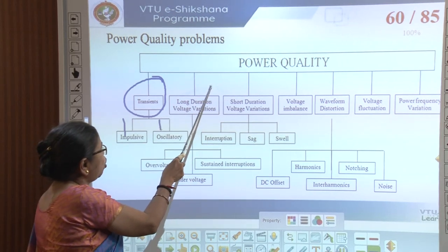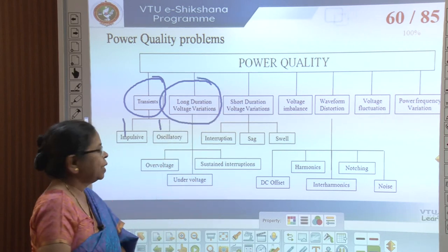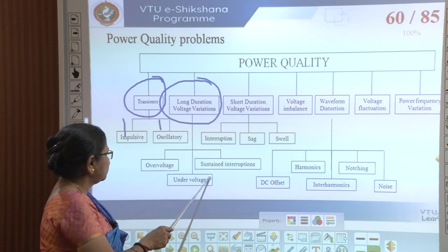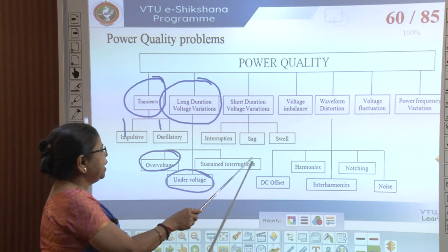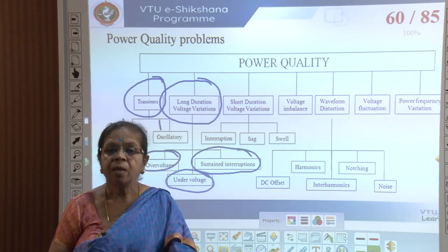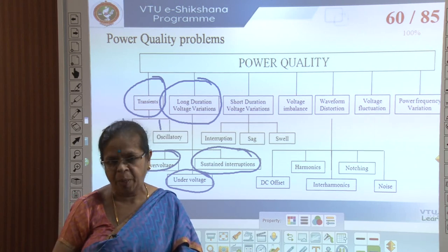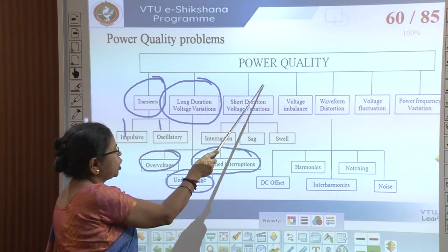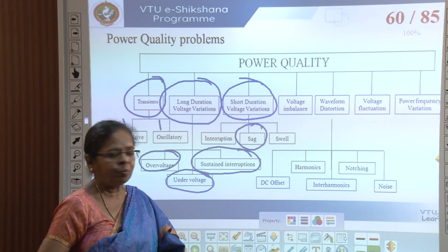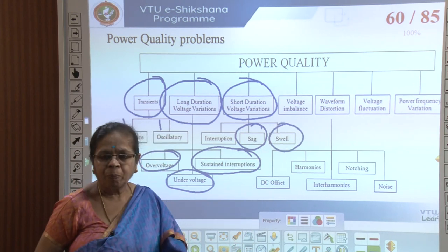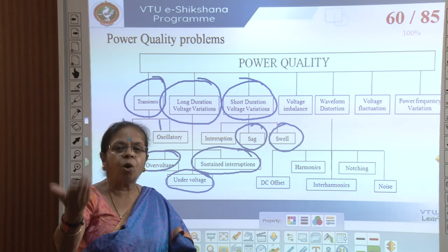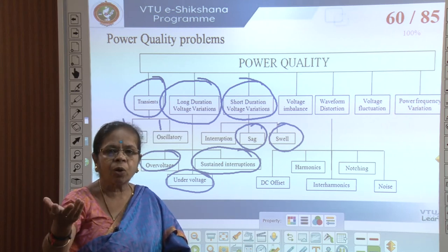The second type is long-duration voltage disturbance, lasting for a longer time. This includes over-voltage, under-voltage, and sustained interruption. Under-voltage means less than specified, over-voltage means more than specified, and sustained interruption means loss of power for a significant time. Then we have short-duration voltage variations: sag means reduced voltage for a short duration; swell means increased voltage for a short duration; and a short interruption lasts for something like 30 seconds. A sag that lasts longer becomes an under-voltage; a swell that lasts longer becomes an over-voltage.